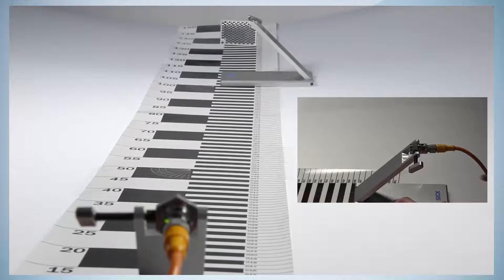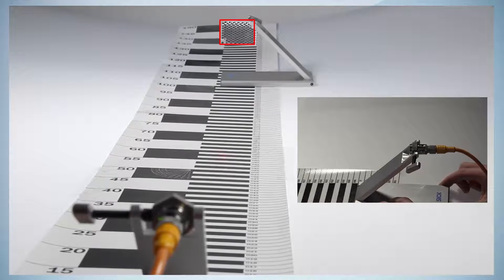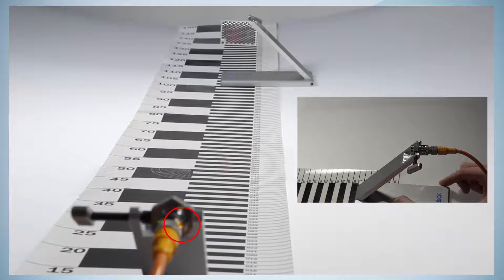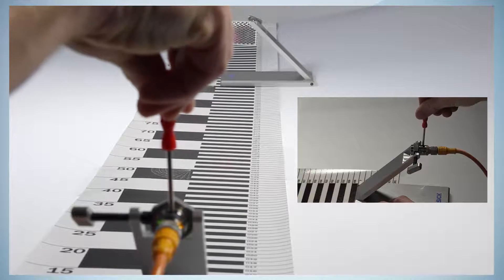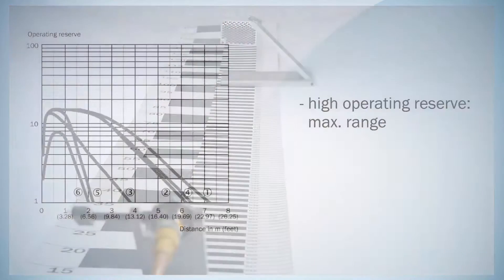During installation, make sure that the light spot is aligned in the center of the reflector. The orange indicator LED will light up continuously if the sensor is aligned correctly. If the sensor includes an adjustment possibility, for example using a potentiometer, adjust the sensor according to your application.